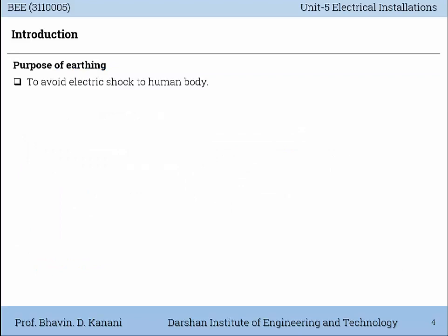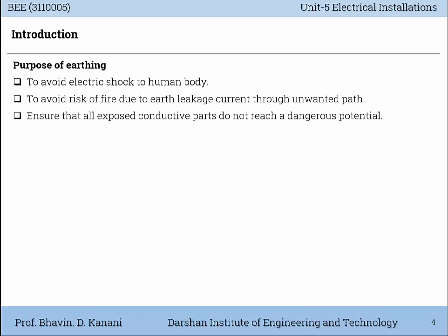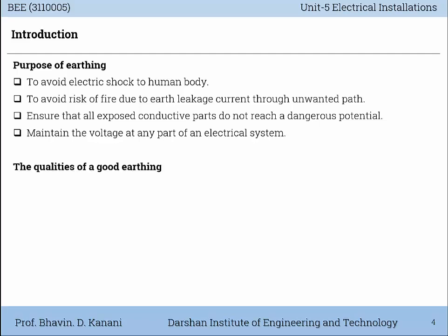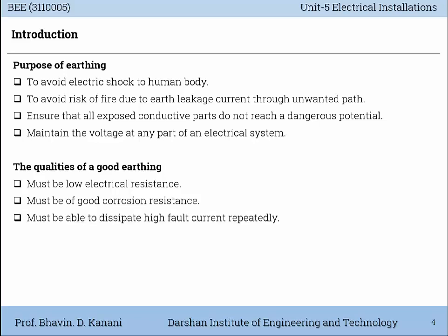Purpose of earthing: to avoid electric shock to the human body, to avoid the risk of fire due to earth leakage current through an unwanted path, to ensure that all exposed conductive parts do not reach a dangerous potential, and to maintain the voltage at any part of an electrical system. The qualities of a good earthing: it must have low electrical resistance, it must have good corrosion resistance, and it must be able to dissipate high fault current repeatedly.